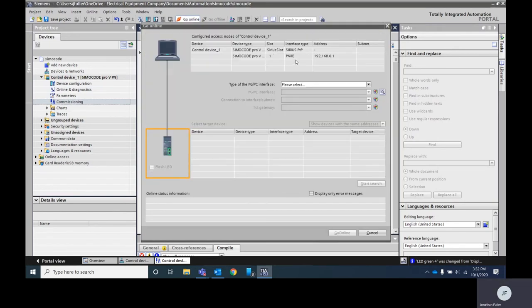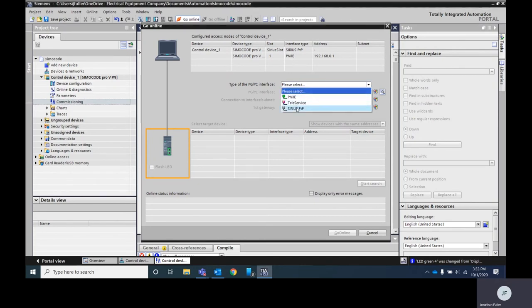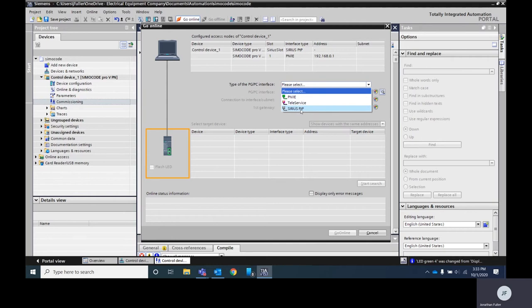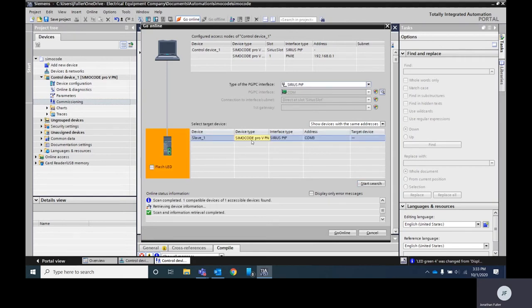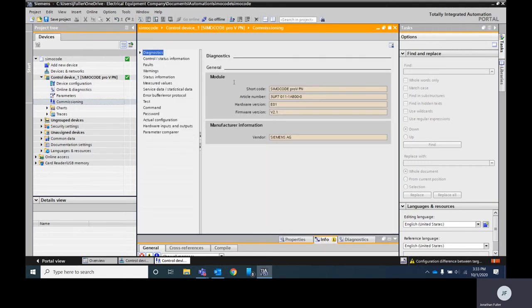We're going to hit the go online button. You've got a couple of different options depending on the software and the type of SIMOCODE you have. For mine I'm doing the USB connection but you also have the option of doing the PROFINET interface. We're going to select this type of interface that we're using whether it's PROFINET, Teleservice, or peer-to-peer. I'm going to do the P2P and then I'm going to hit start search. There it's found it. I'm going to hit go online.